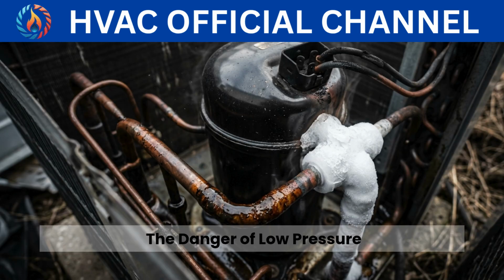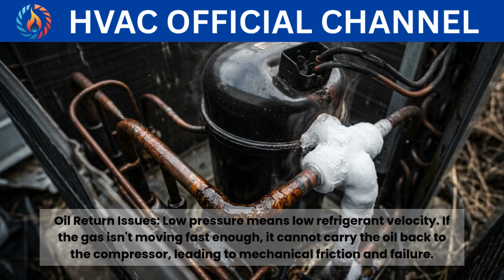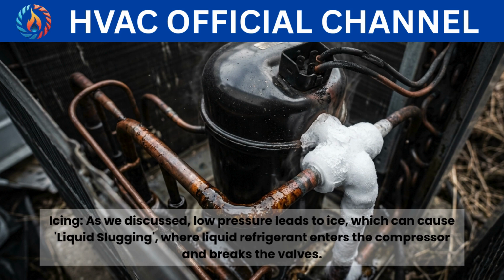The danger of low pressure. Why should we care? Compressor burnout. The compressor motor is cooled by the returning suction gas. Low pressure often means low density, which leads to the motor overheating. Oil return issues. Low pressure means low refrigerant velocity. If the gas isn't moving fast enough, it cannot carry the oil back to the compressor, leading to mechanical friction and failure. Icing. As we discussed, low pressure leads to ice, which can cause liquid slugging, where liquid refrigerant enters the compressor and breaks the valves.